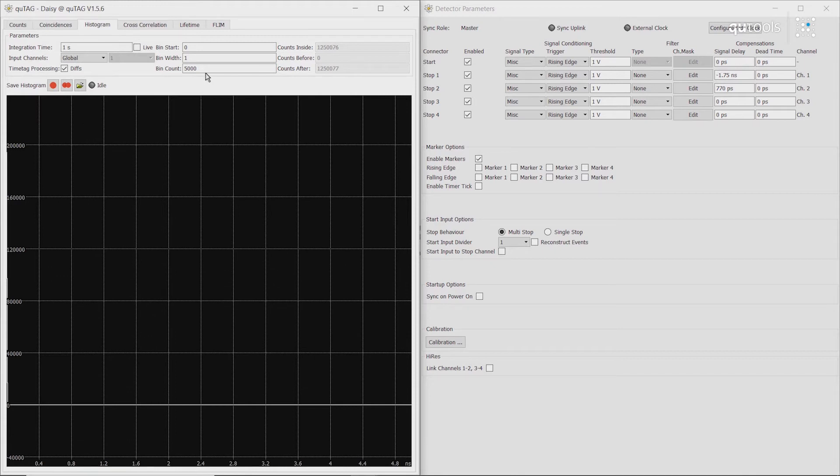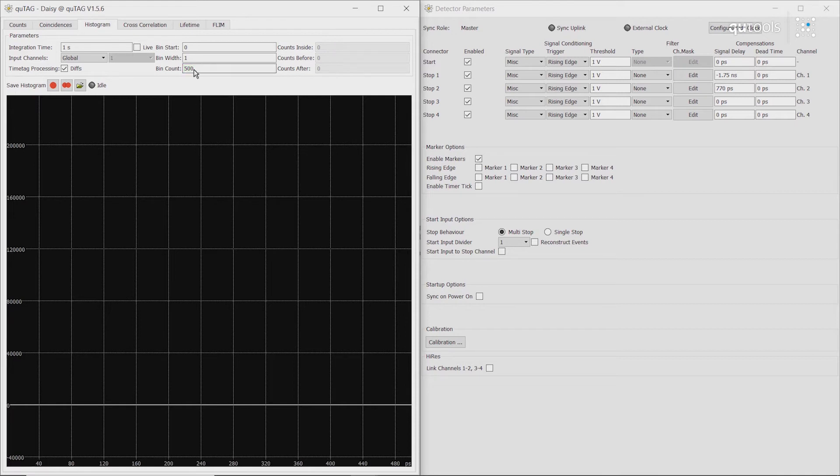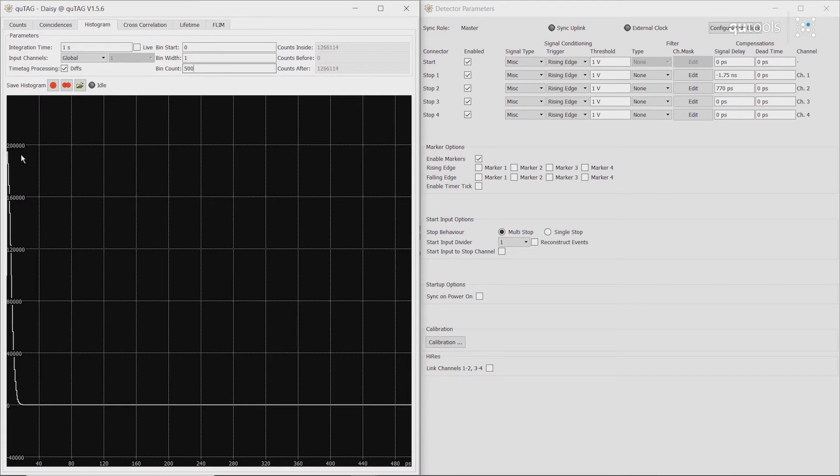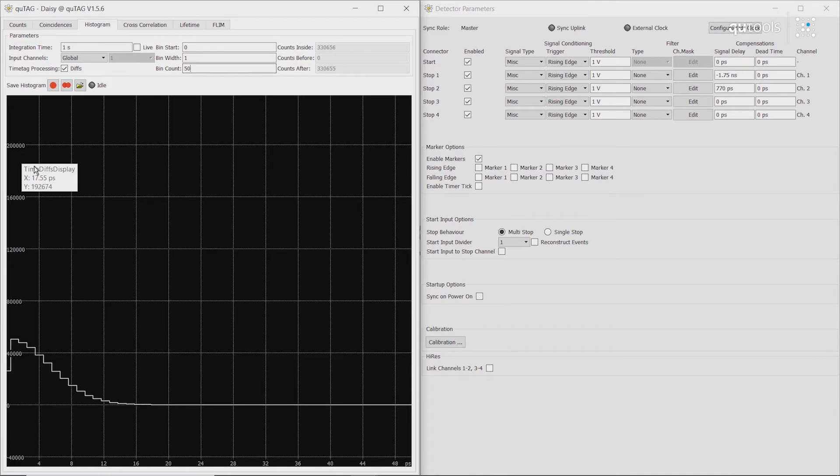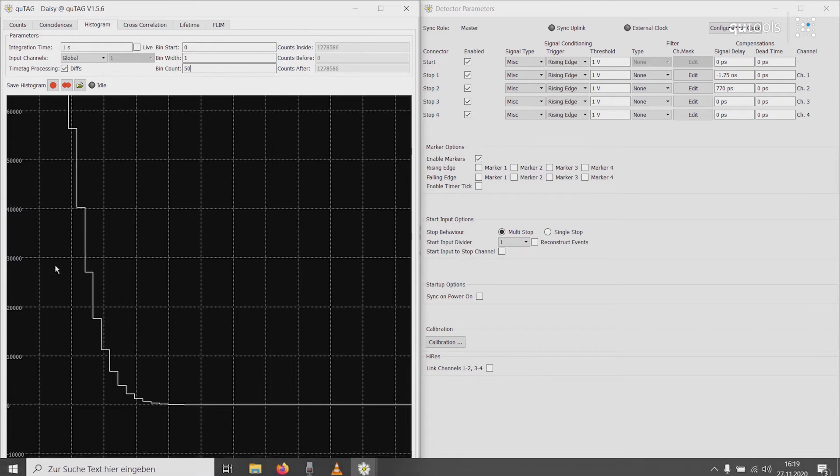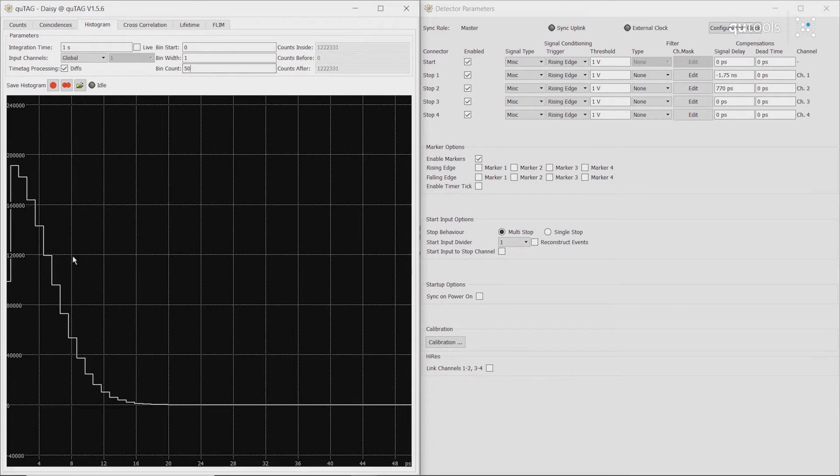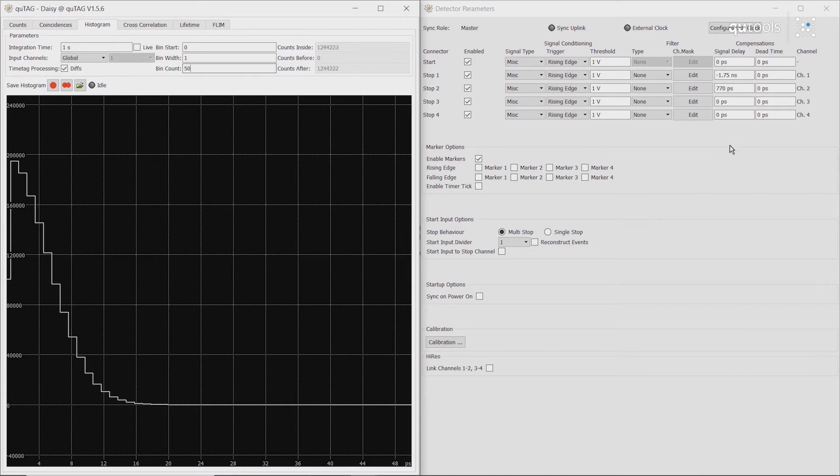So if we switch this back, and we then adjust our bins again, we can see that our histogram is now centered around 0. So we've now corrected for the different cable lengths of the two channels.